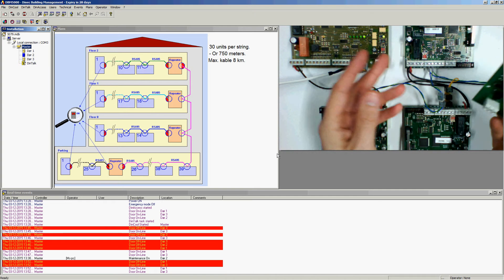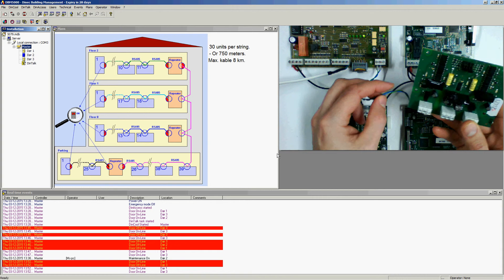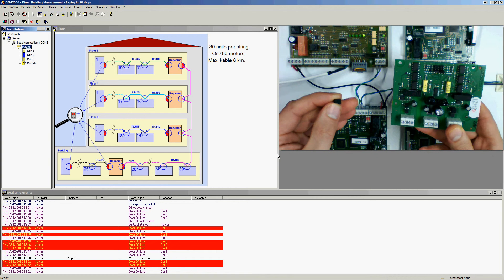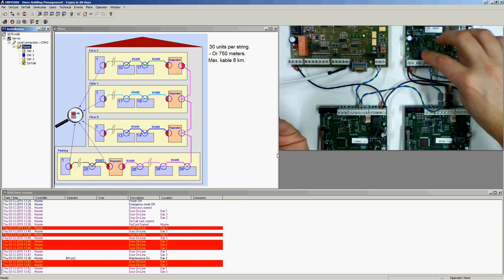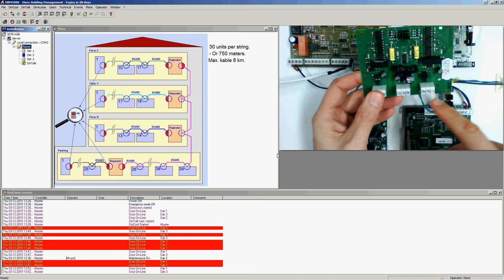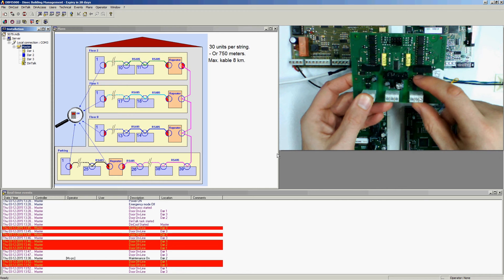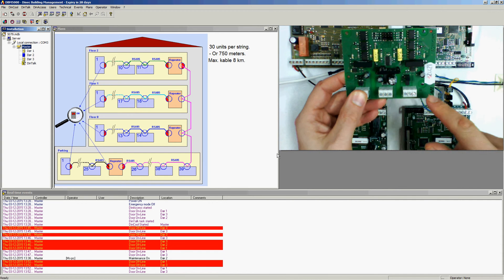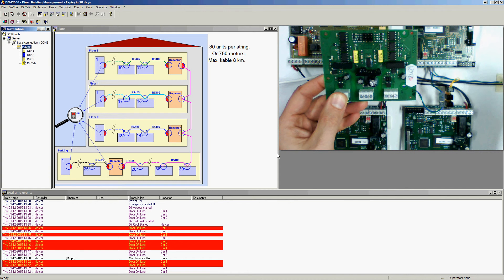On the output side I would have to choose: am I starting the bus with the repeater here? If I do that, the jumpers have to be on. If instead my starting door is to the left — with a few doors and then a few more doors — then the last door there would be the true end of line. In that case, the termination of the repeater should also be without jumpers.